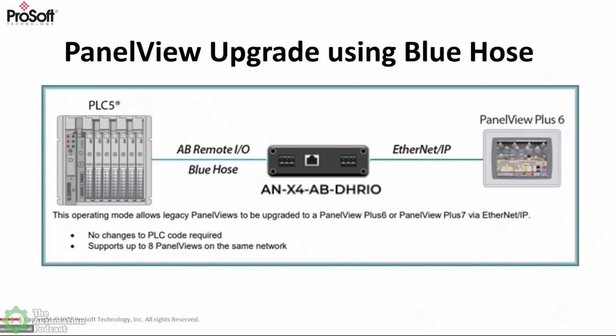This one I think would probably be the trickiest to do. So you've got a PLC5 or SLC 500, more likely a PLC5, and on its Blue Hose it used to talk to a legacy panel view on remote I/O, which was always painful to program. Now you can put the AN-X4 in and put a panel view plus on Ethernet, mapped to the old remote I/O where the old panel view used to be, so you don't have to change anything.